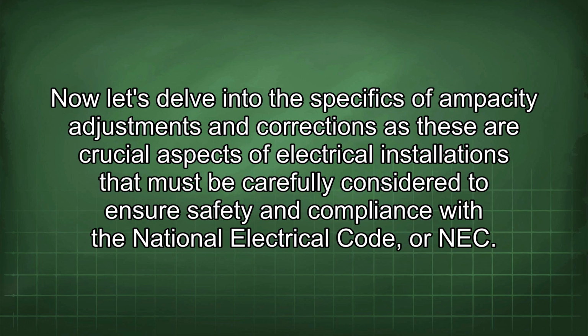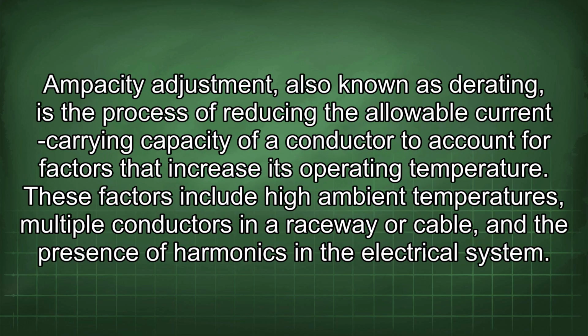Now let's delve into the specifics of ampacity adjustments and corrections, as these are crucial aspects of electrical installations that must be carefully considered to ensure safety and compliance with the National Electrical Code, or NEC. Ampacity adjustment, also known as derating, is the process of reducing the allowable current carrying capacity of a conductor to account for factors that increase its operating temperature.